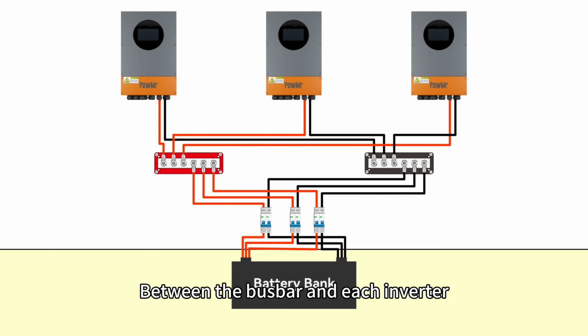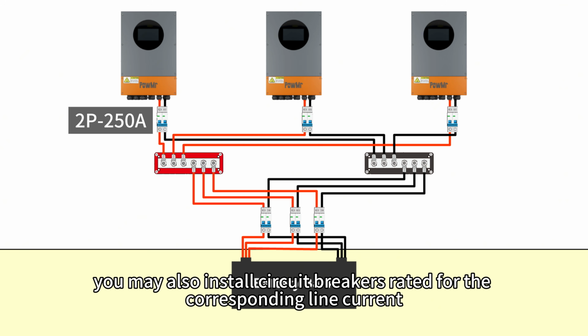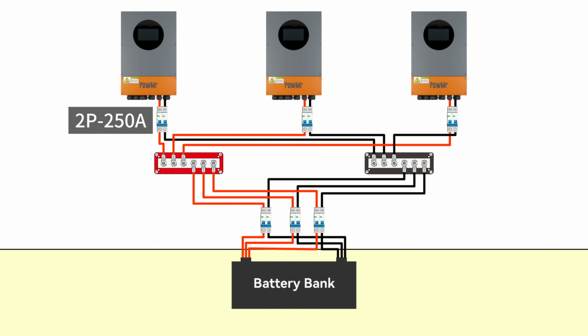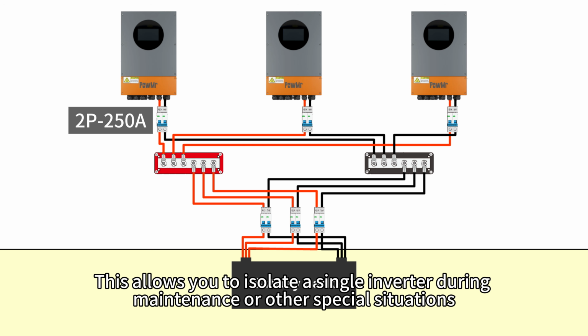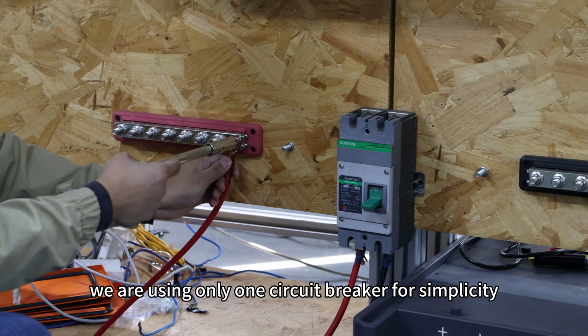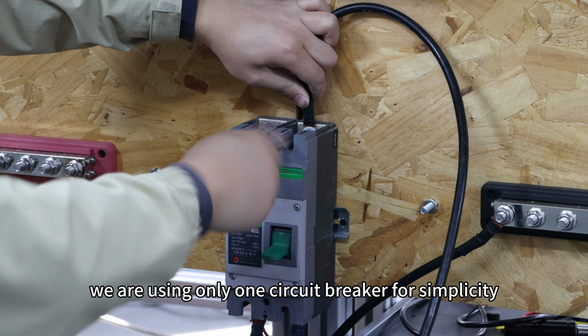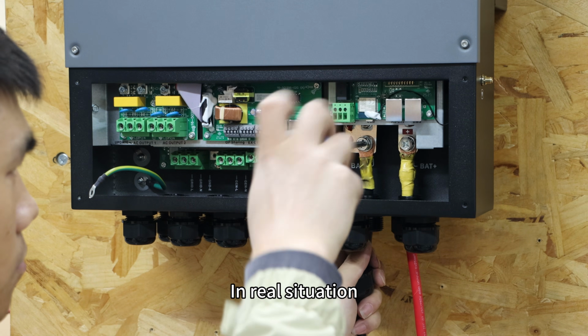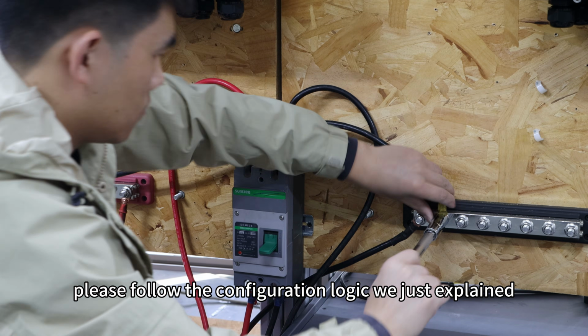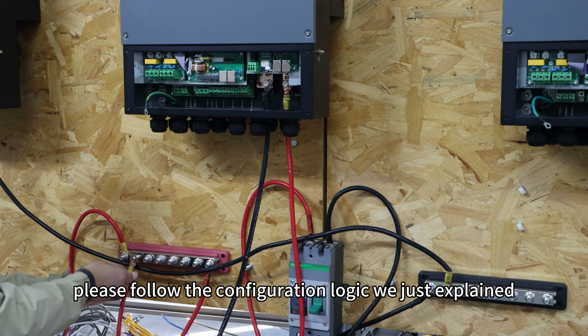Between the bus bar and each inverter, you may also install circuit breakers rated for the corresponding line current. This allows you to isolate a single inverter during maintenance or other special situations. For this demonstration, we are using only one circuit breaker for simplicity. In real situations, please follow the configuration logic we just explained.